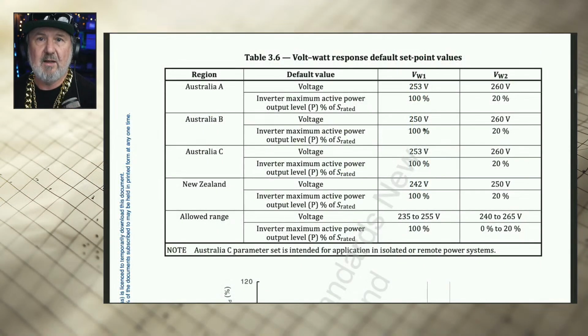Okay. So this is a table that comes from 4777 Part 2. Now, AS/NZS 4777 Part 2 is a test standard that all inverter systems connected to the Australian or the New Zealand electricity grid need to comply with. And there are some default settings. You'll notice in the regions on the left-hand side, we've got Australia A, B, and C. So they're different regions, like A down here in Victoria. I can't remember which B and C are. One of them's Western Australia and one of them's sort of northern parts of Australia, like Queensland, I think. And then, of course, we've got New Zealand, and then there is an allowable range. Now, that means the range at which it must not go outside of, or the inverter has to disconnect completely. And inverters have to respond in a certain time frame, and the time frames also vary depending on the amount of voltage mismatch from nominal.